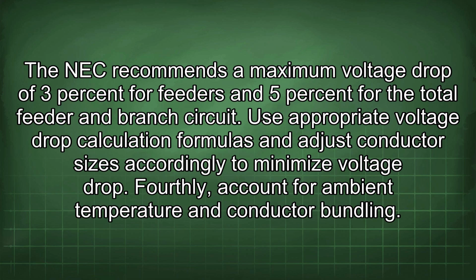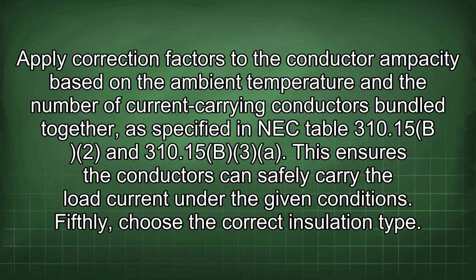Fourthly, account for ambient temperature and conductor bundling. Apply correction factors to the conductor ampacity based on the ambient temperature and the number of current carrying conductors bundled together, as specified in NEC Table 310.15(B)(2) and 310.15(B)(3). This ensures the conductors can safely carry the load current under the given conditions.